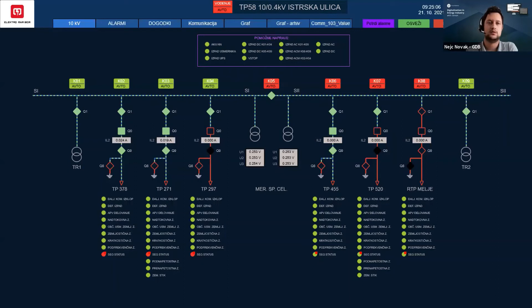Let's talk for a minute about how signals come from protection relays to the distribution center. First it goes from a protection relay through an optical cable to an optical converter, where this converts to a serial connection using standard IEC 60870-5-103, and then gets to Zenon Service Studio. From there we go through a process gateway with an IP connection using the 104 standard to the distribution center in Elektro Maribor.